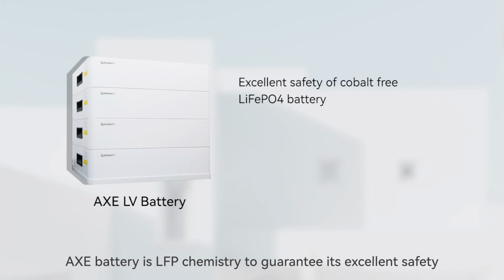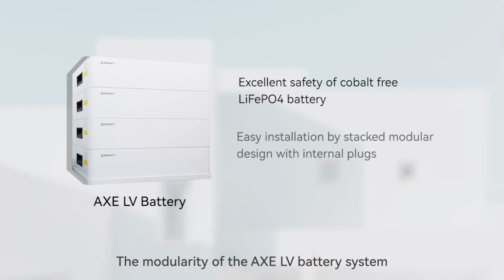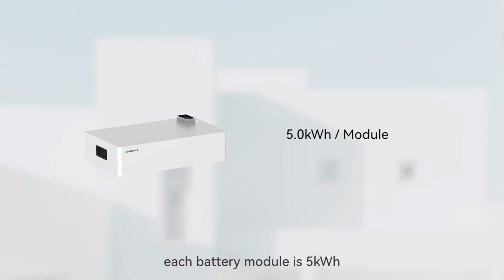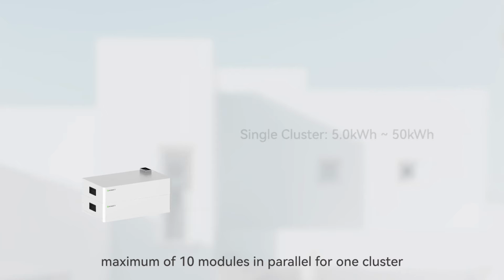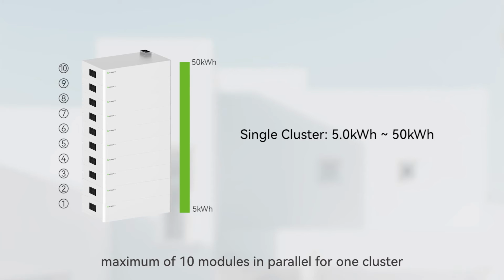AXE battery is LFP chemistry to guarantee its excellent safety. The modularity of the AXE LV battery system makes it easy to install with internal plugs. Each battery module is 5 kWh. Maximum of 10 modules in parallel for one cluster. The capacity of a single cluster could reach 50 kWh.